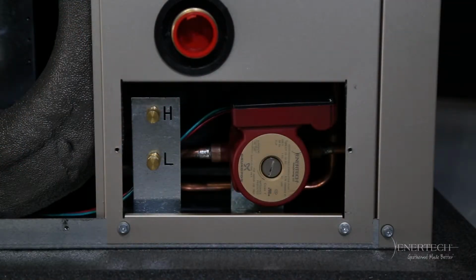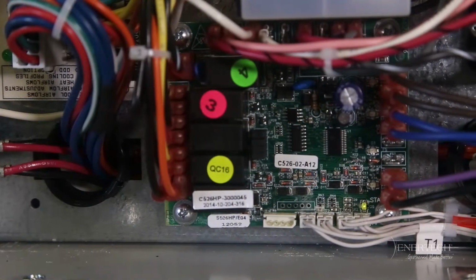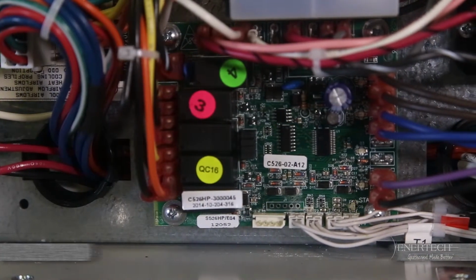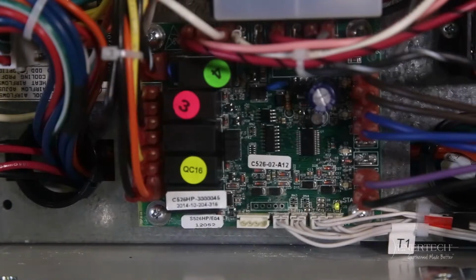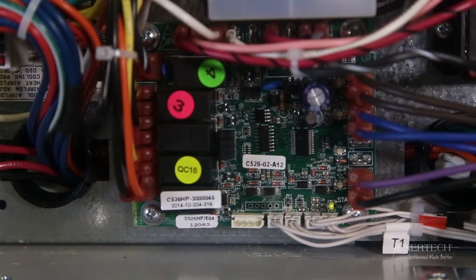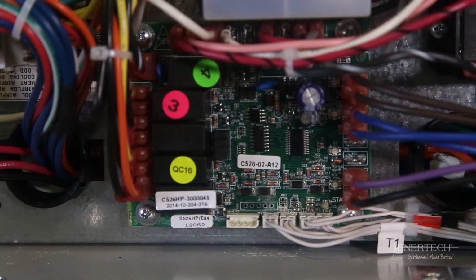All these issues will break the circuit of the HWG pump via the HWG signal from the lockout board, but will not lock out the compressor except when T2 is greater than 220 degrees Fahrenheit. Units without a HWG also do not have sensors T2 and T3. The control ignores T2 and T3 and disables faults 15 and 16, sensor bad.